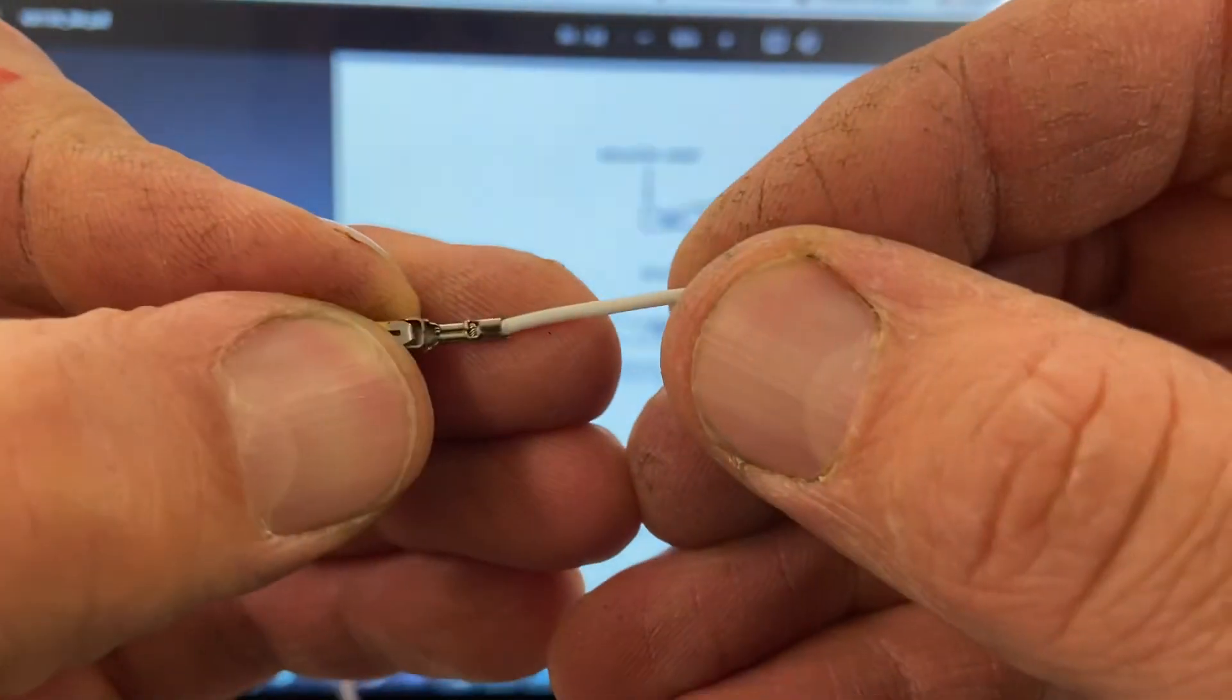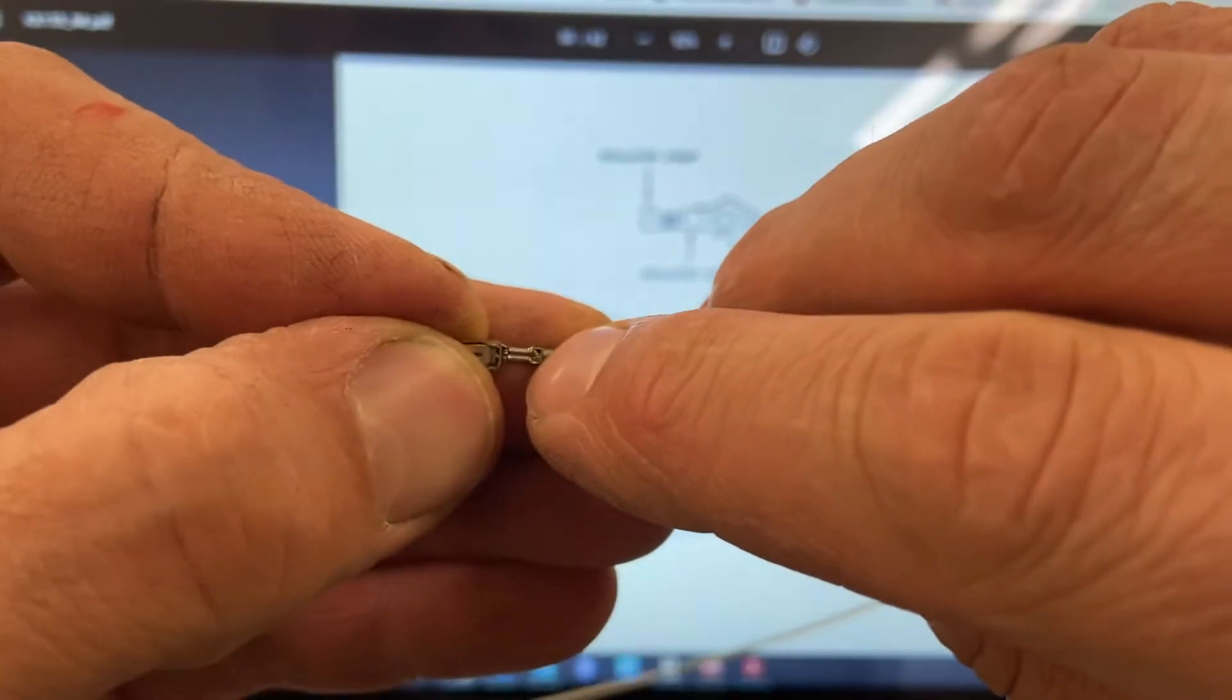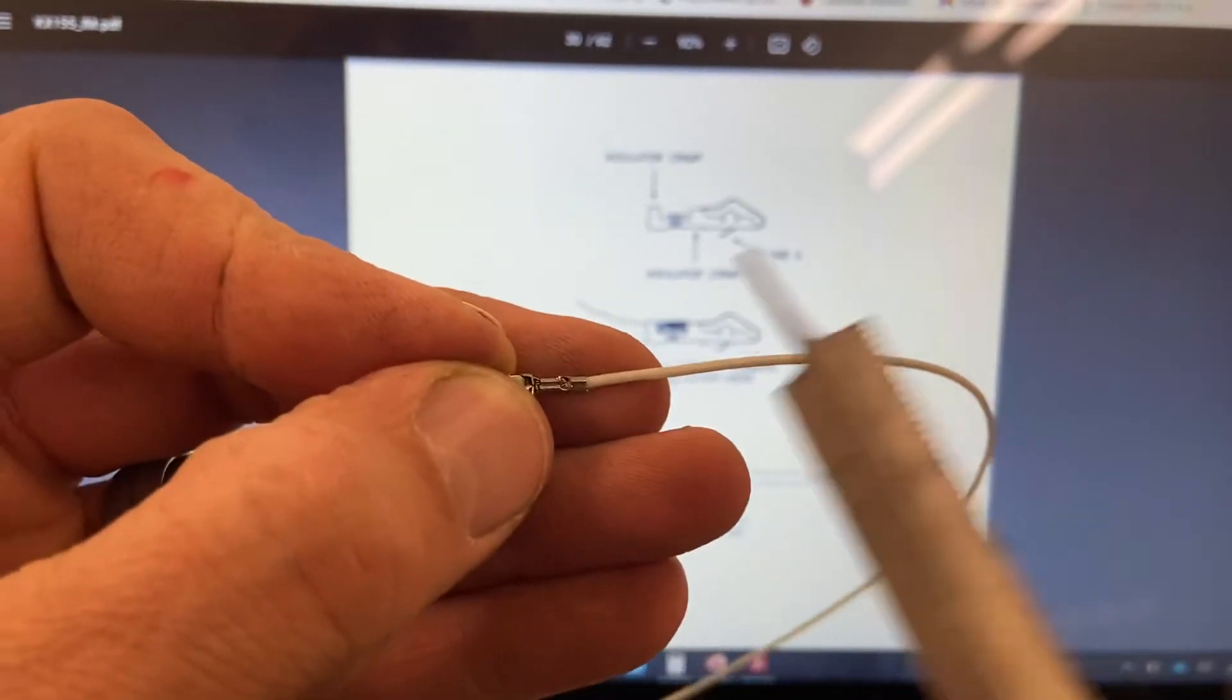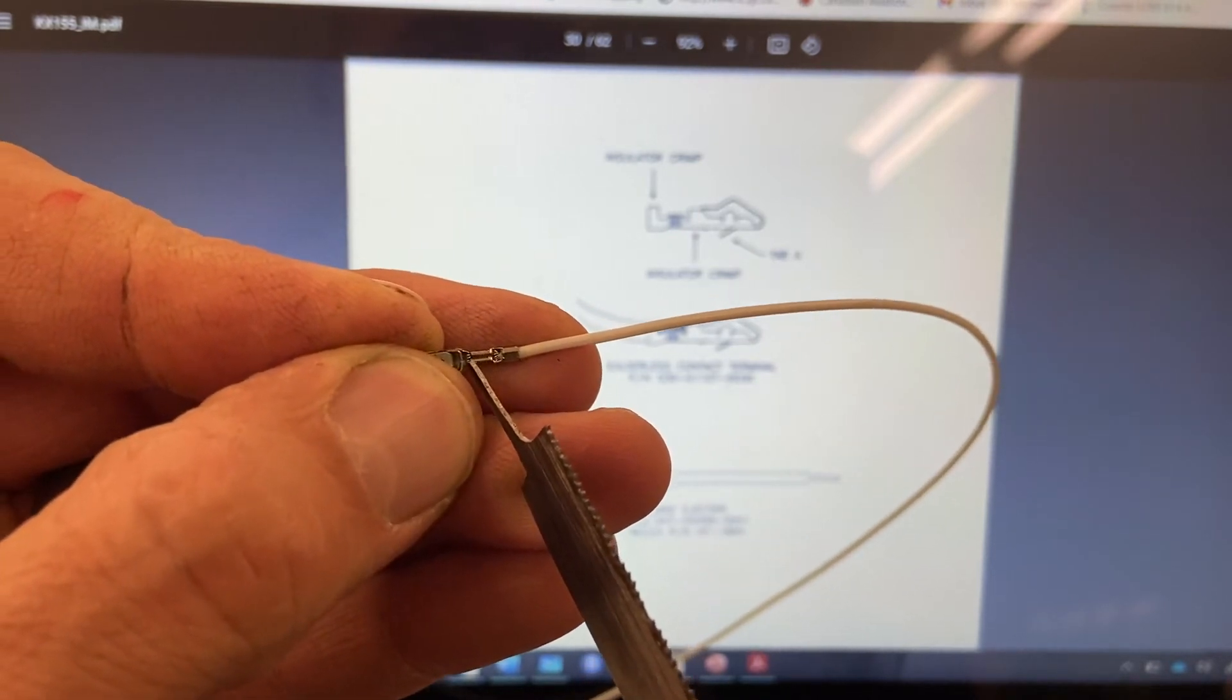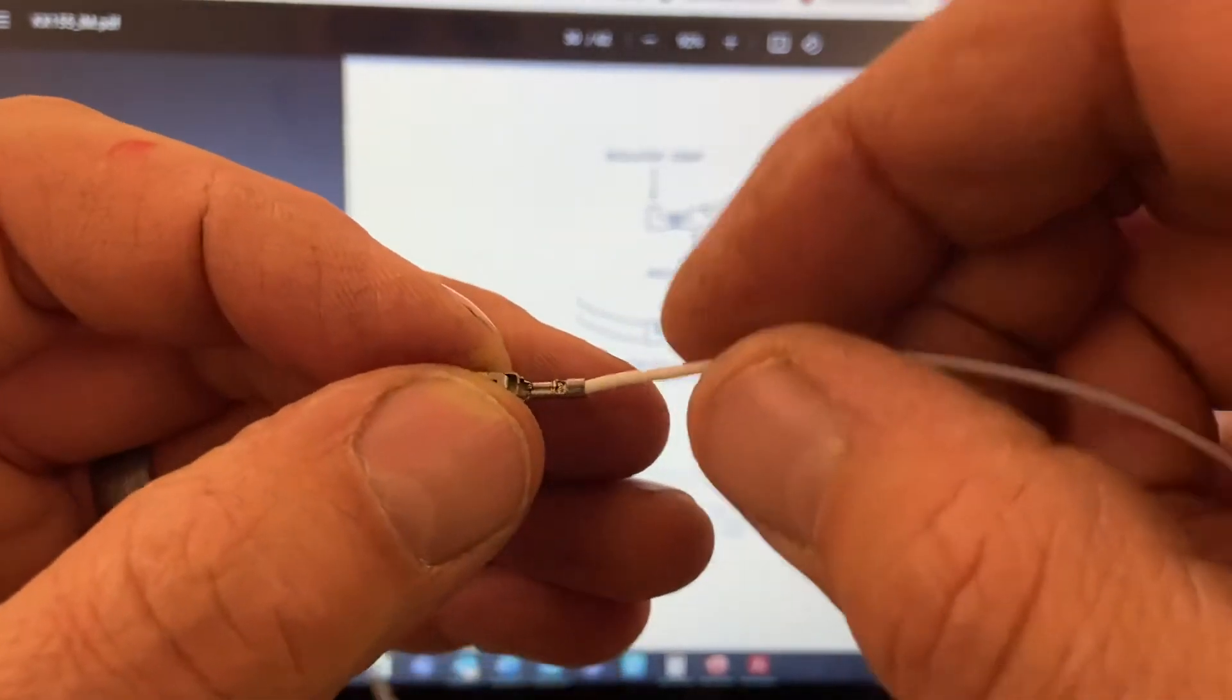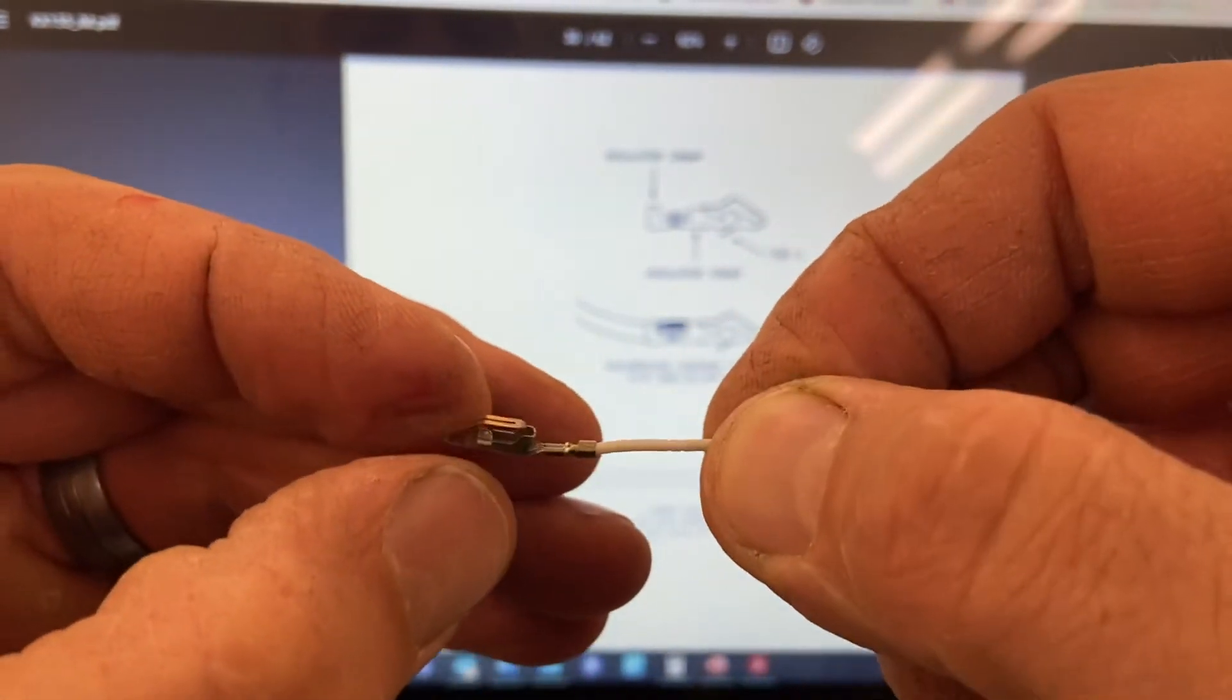I can see that I've got a bit of white here, which shows that the shielding has gone all the way through. And I've got a little bit of wire sticking out the end, which shows that the wire extends through the crimped portion. If I pull on this, it's going to give me the desired strength I need.